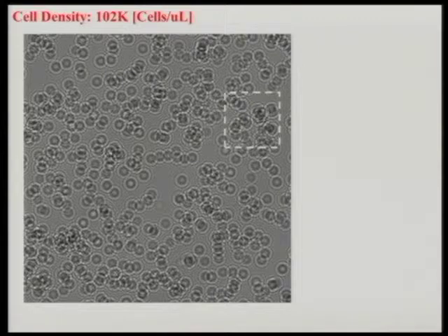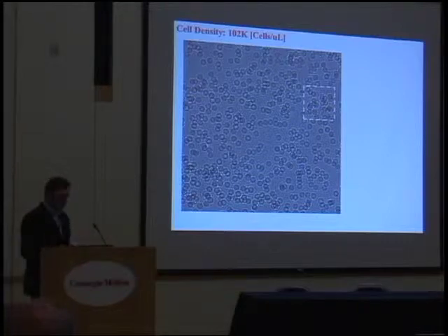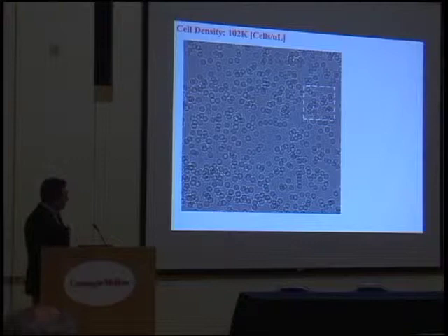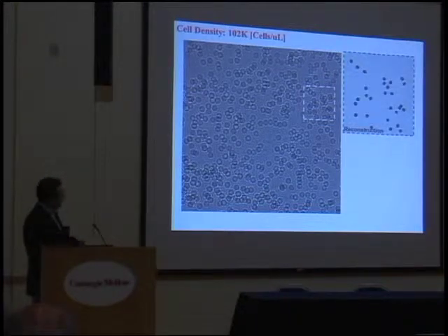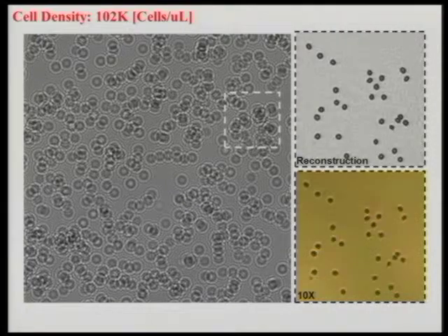But that's the time to realize that these dummy-looking shadows are actually quite rich in terms of what they contain, because they contain the interference of the scattered light from the three-dimensional body of the cell with the background light, and that is actually a hologram. So you can actually treat these dummy-looking shadows as holograms, inline holograms of the specimen, and reconstruct their images, in this case red blood cells, and compare against the regular microscope, but of course over a much larger area, a much larger field of view compared to a conventional microscope, because now you're not restricted to objective lenses.